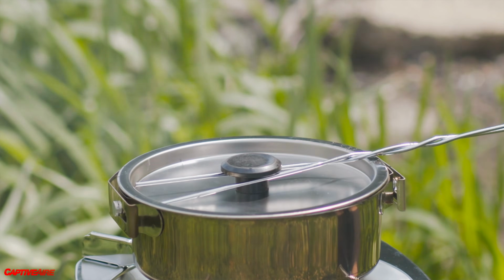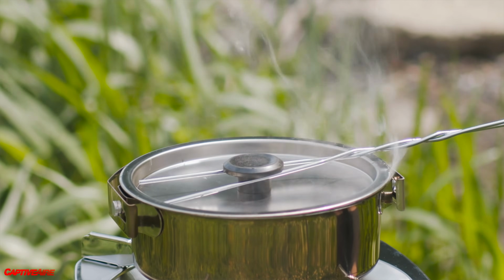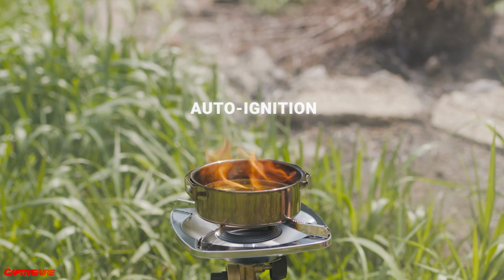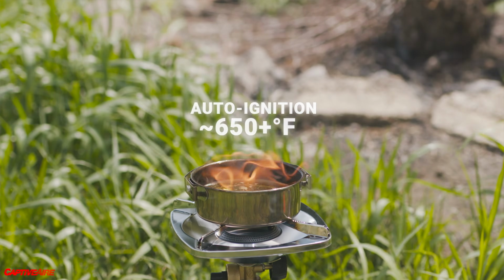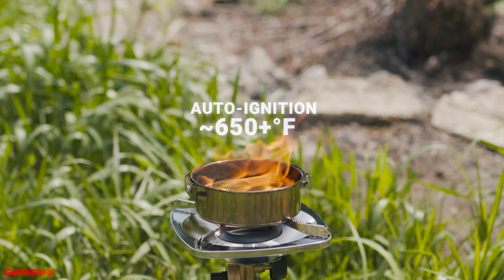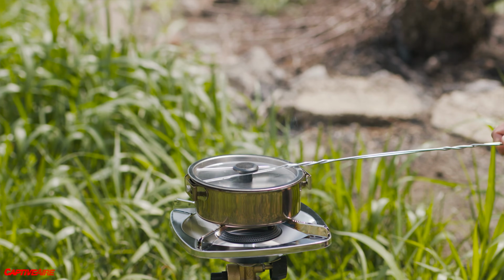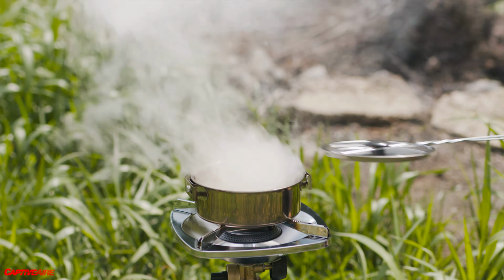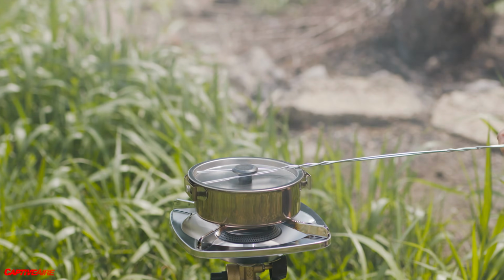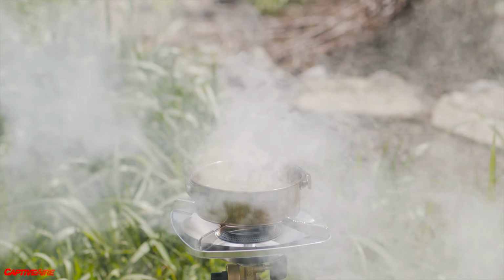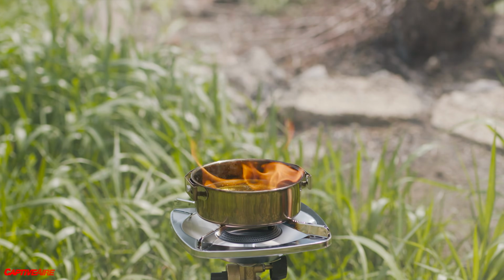There's one more temperature point, and if you reach this, you really messed up, and it's called auto ignition. At this point, there's so much heat from the oil and so much oil vapor in the air that the thing lights up on its own. And if I suffocate it now, it'll go out, but the oil is hot enough that it will just reignite again. This is why dry chemical systems are no longer used in kitchens.